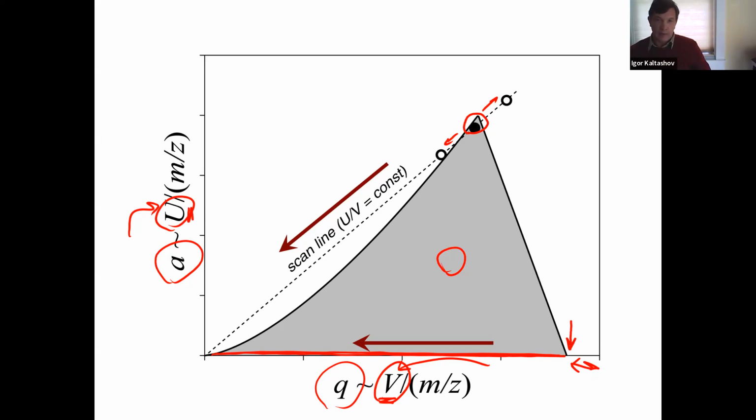We frequently use quadrupoles, not just as standalone instruments, but as ion storage devices, so ion guides. And in fact, this assembly that I showed you earlier was not taken from a real quadrupole instrument. It's the quadrupole part of the so-called QTOF, quadrupole time of flight, a hybrid instrument where you have a first stage, a quadrupole filter.